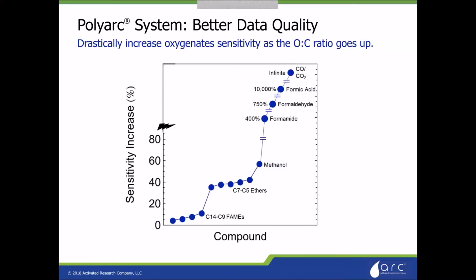So one thing I want to talk about that I mentioned earlier was the increase in sensitivity. So are you going to see an increase in sensitivity? That depends on what molecules you're looking at. The FID already does a fantastic job at burning and combusting hydrocarbons, olefins, straight chain hydrocarbons, paraffins. And those are already pretty much a uniform response per carbon to methane as they go through the FID. So you're not going to see a big increase in sensitivity for those hydrocarbons. However, when you start to add oxygen, as you can see with these FAMEs, as you go from a C9 or C14 up, that oxygen to carbon ratio changes, and you start to lose sensitivity in a normal FID, which means we can gain that sensitivity back by converting it to methane.